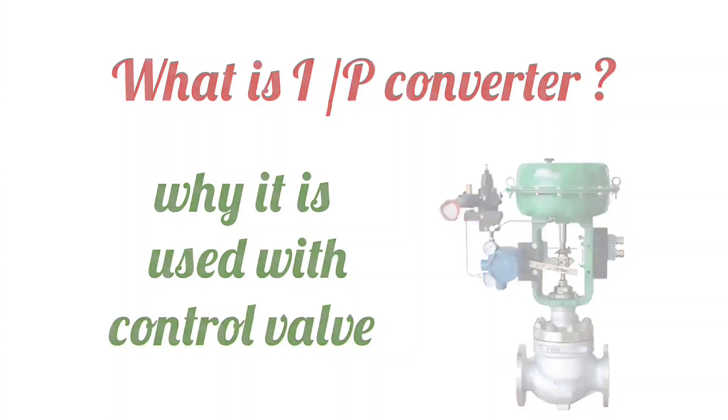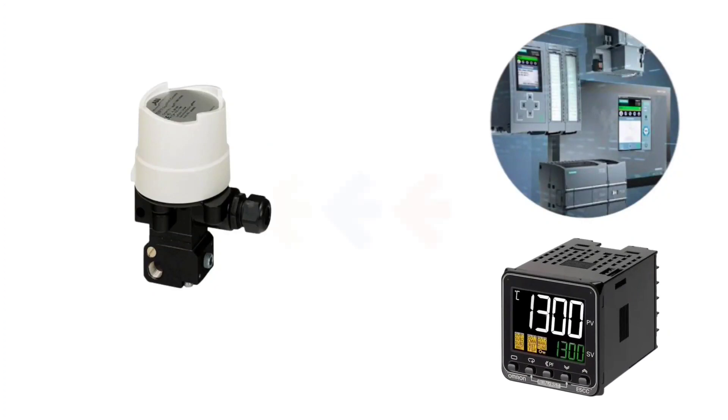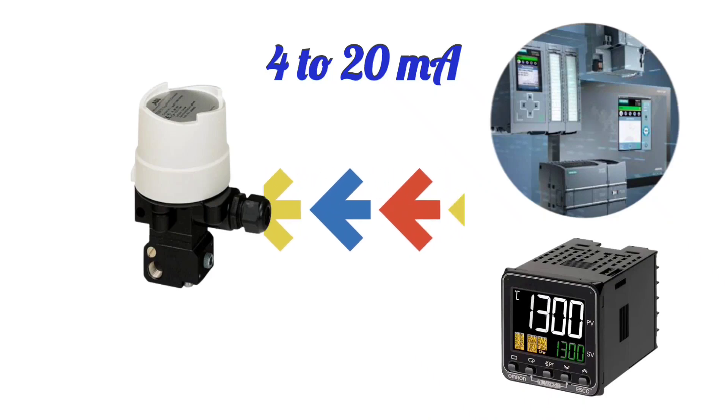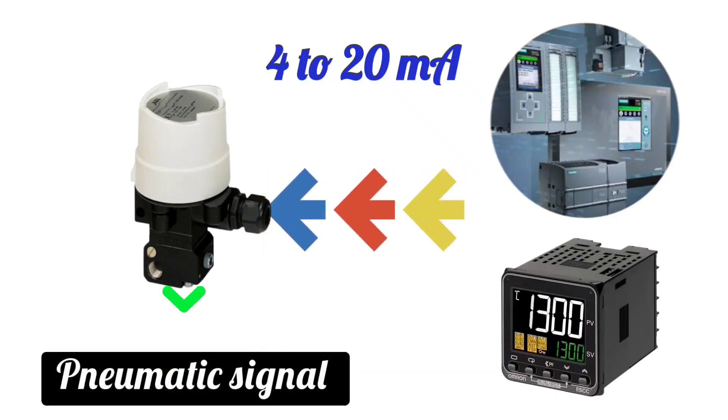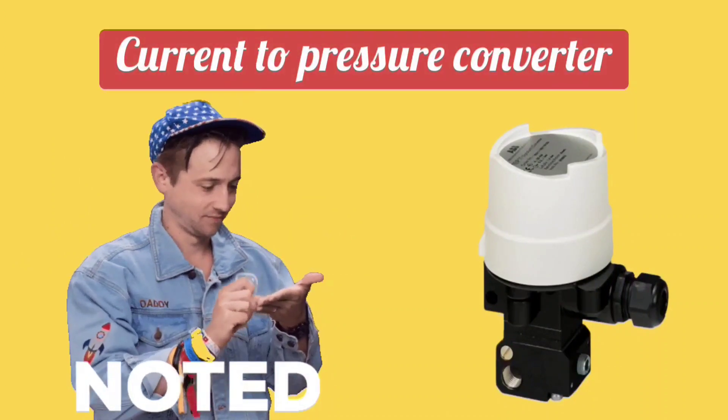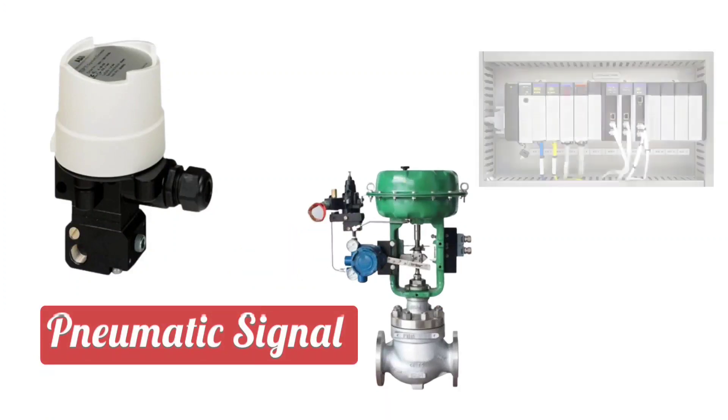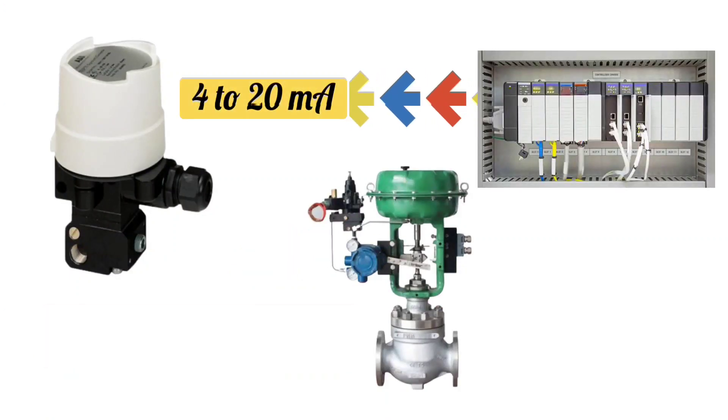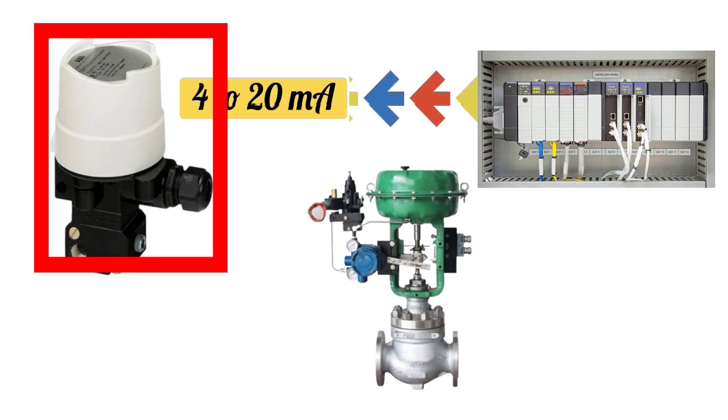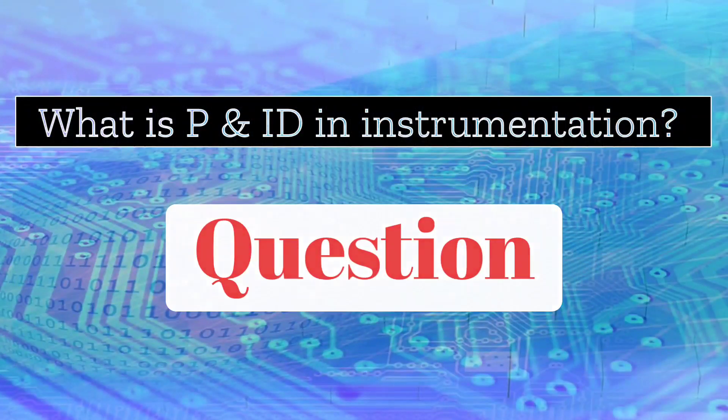Let's see the next question: What is I/P converter? Why use it with control valve? The function of I/P converter is to convert the current signal coming from PLC or PID controller, which is 4 to 20 mA, into pneumatic signal. That's why it is also called current-to-pressure converter. From the I/P converter, the pneumatic signal is given to the control valve. To make the control valve operate according to 4 to 20 mA, I/P converter is used.